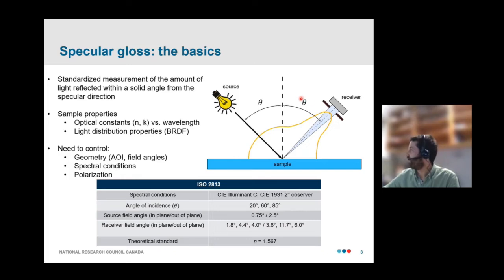Now, in general, this measurement will depend on the optical constants of the material. It'll depend on their dispersion with wavelength, and it's also going to depend on their light distribution properties. So in order to obtain a meaningful measurement that can be compared between instruments, it's important that the experimental conditions related to geometry, by that I mean the angle of incidence and the field angles, the spectral conditions and the polarization of the measurement device are all well controlled.